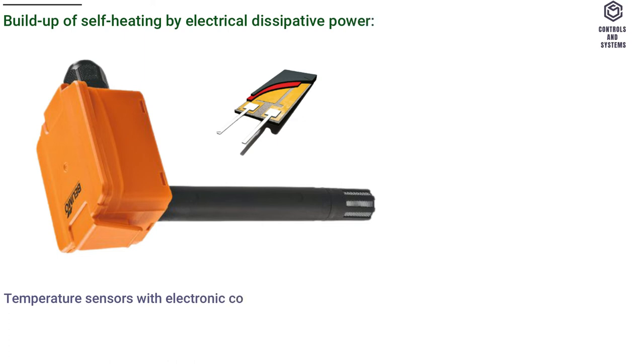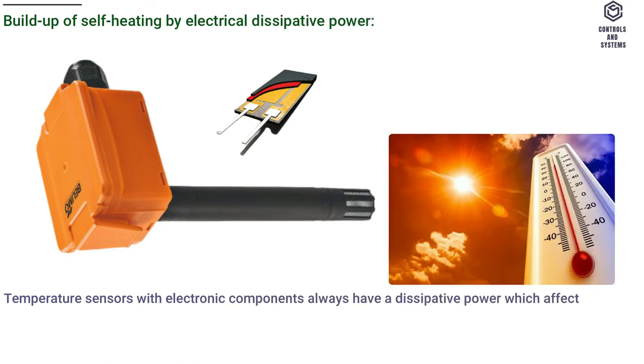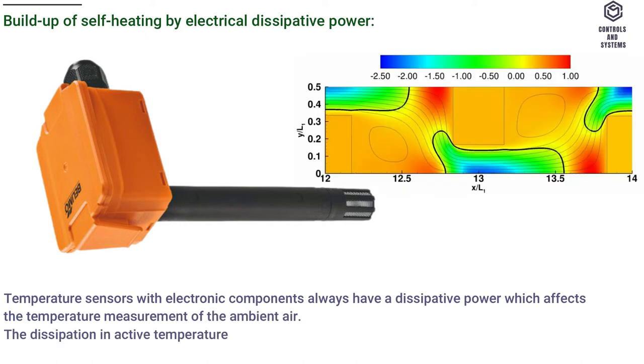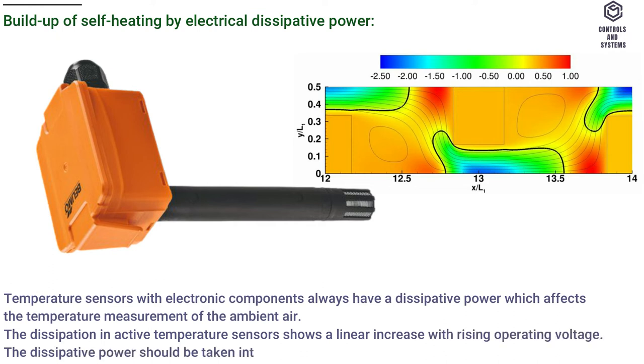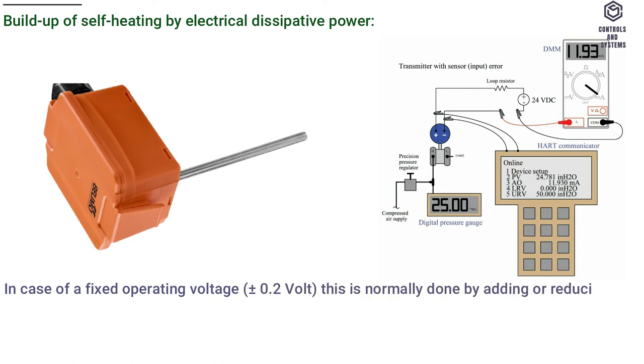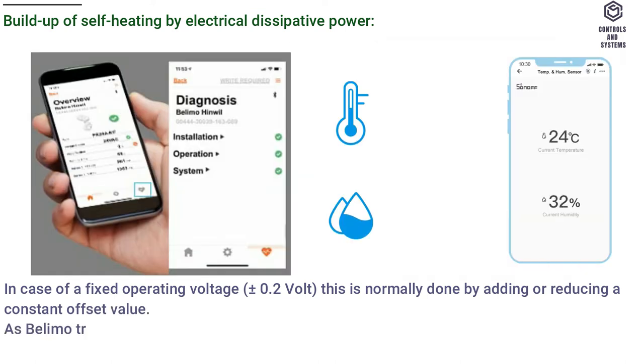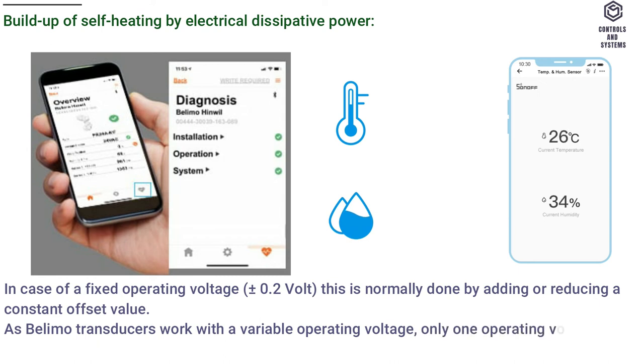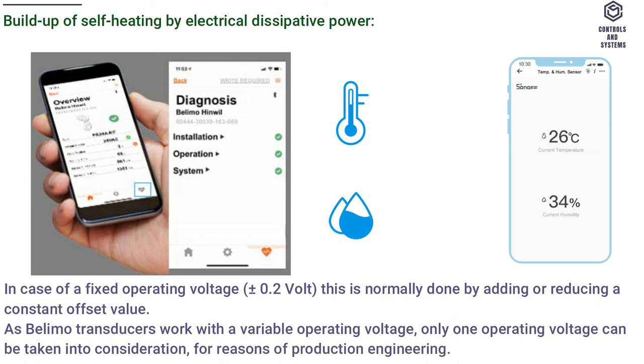Buildup of self-heating by electrical dissipative power: Temperature sensors with electronic components always have a dissipative power which affects the temperature measurement of the ambient air. The dissipation in active temperature sensors shows a linear increase with rising operating voltage. The dissipative power should be taken into account when measuring temperature. In case of a fixed operating voltage of ±0.2 volt, this is normally done by adding or reducing a constant offset value. As Belimo transducers work with a variable operating voltage, only one operating voltage can be taken into consideration for reasons of production engineering.